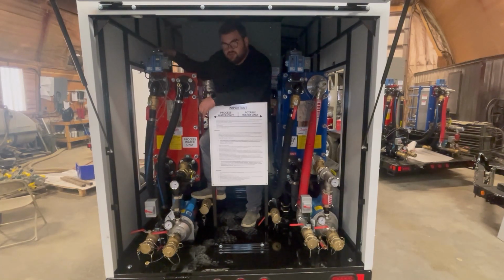We have an actuated valve at the top of the glycol that measures water temperature on the opposite side of your plate. It closes and opens as your water temperature reaches your set point of where you want your water. So it delivers hot glycol all the time until you start getting close to the water temperature that you want to achieve, and it slowly closes off and allows glycol to maintain a water temperature.